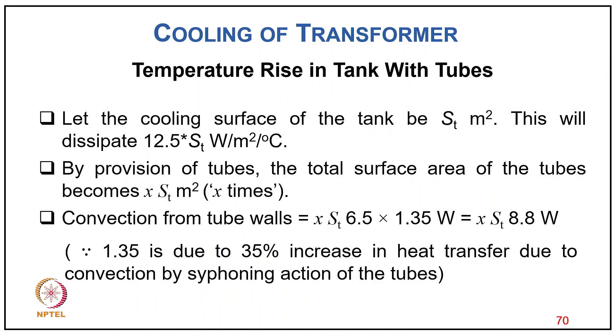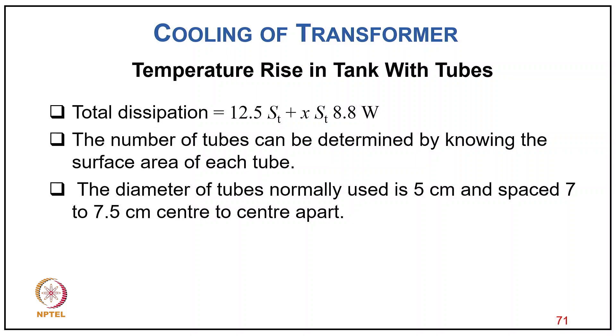For temperature rise in a tank with tubes: let the cooling surface of the tank be ST m². This dissipates 12.5×ST W/°C. With tubes of surface area X×ST m², convection from the tubes = X×ST×6.5×1.35 = 8.8×X×ST W/°C (the 1.35 factor is due to 35% increase in heat transfer from siphoning action). Total dissipation = (12.5 + 8.8X) × ST W/°C.